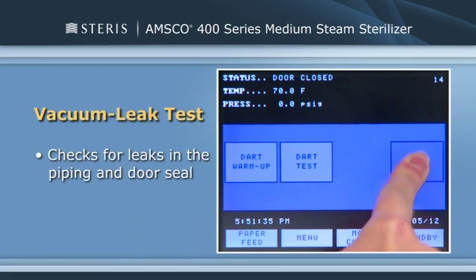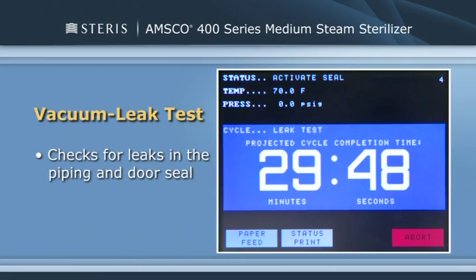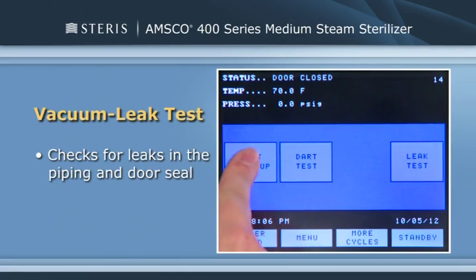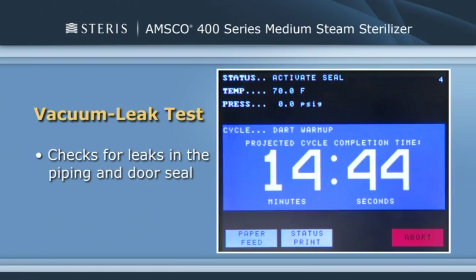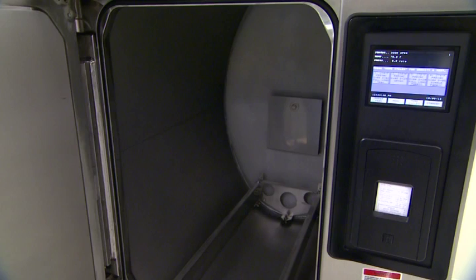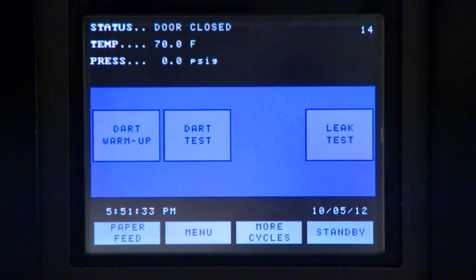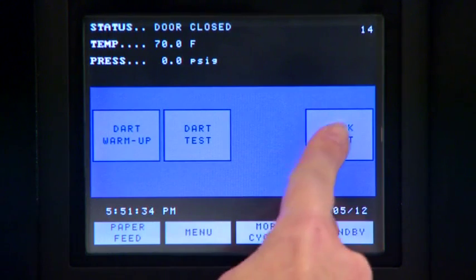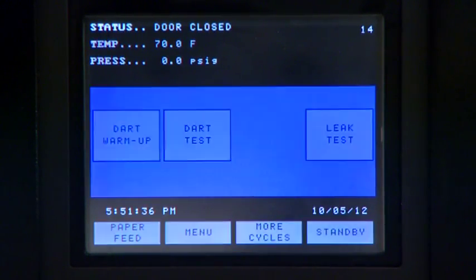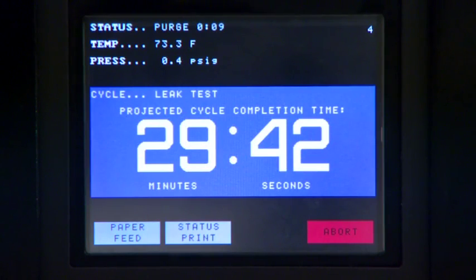The vacuum leak test should be performed at least once a week. It automatically checks for leaks in the piping and door seal. To ensure valid test results, always run a warm-up cycle before performing this test. When the warm-up cycle is finished, initiate the vacuum leak test. The sterilizer chamber must be empty while running this test cycle. From the Test Cycles menu, press the Leak Test button. Again, the vacuum leak test cycle values are pre-programmed and cannot be adjusted.